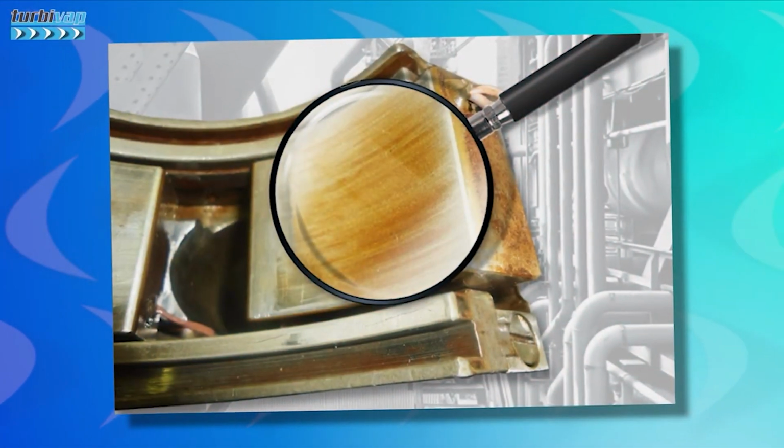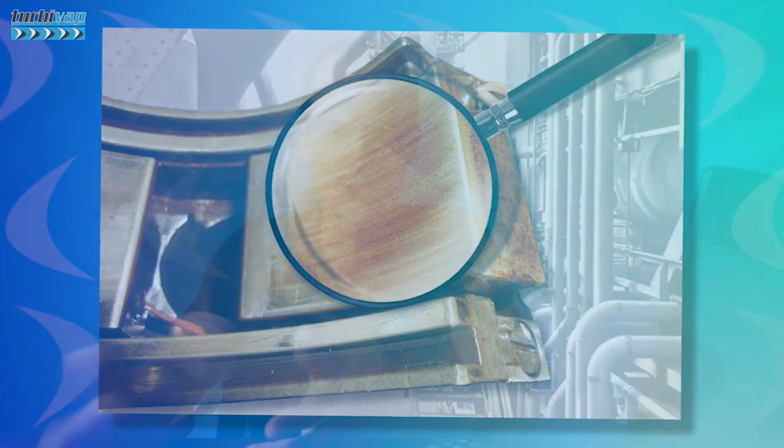For anyone interested in the subject, the oils must release entrained air quickly to help prevent cavitation, but they should also not cause excessive foaming. Rust and corrosion inhibition is a basic necessity to ensure that all major turbine components are protected, mainly in steam turbines, where water contamination is a recurring concern. Turbine oil must be able to separate water effectively and very quickly. If the water cannot be separated from the oil, it can turn into an emulsion of oil and water, which will interfere with the oil film necessary for the loads supported by the bearings.